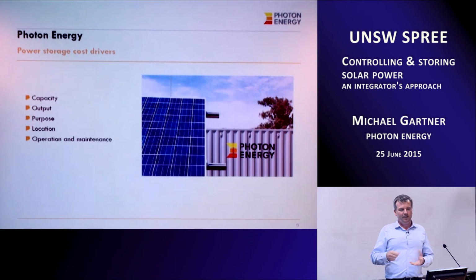So when I see generalizations such as cost per kilowatt hour or cost per kilowatt of output, it doesn't really make much sense, because if you have a system that needs to cover a very high load, you may have 200 kilowatt hours of battery storage and 100 kilowatts of throughput, because you only need bursts of power.